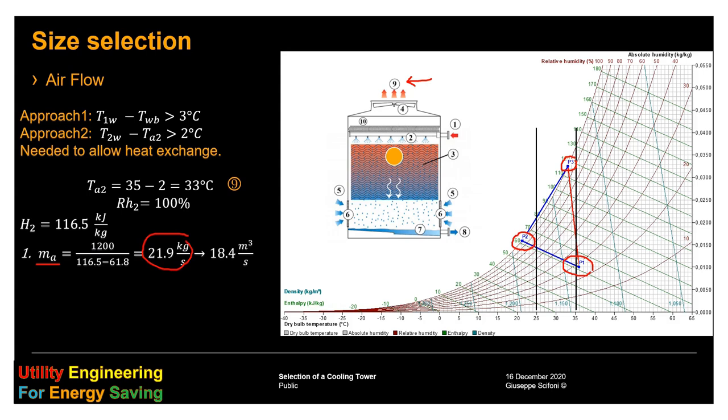But we are not sure that is the right value, because we need to satisfy also the second equation. The mass given by this equation is a little bit higher, 22.2. The mass balance says that the water evaporated is increasing the humidity of the air. The humidity we can read also from the chart. This is the starting value, and this is the leaving value of the stream.